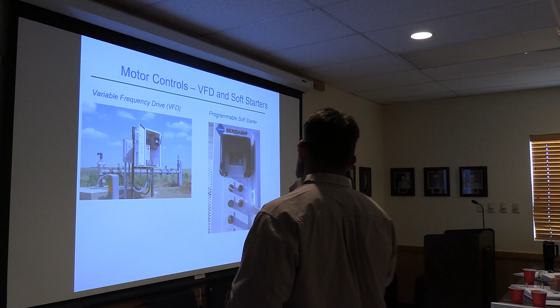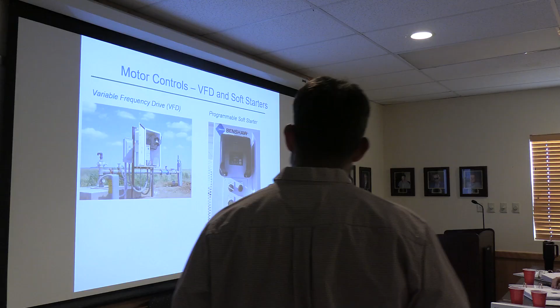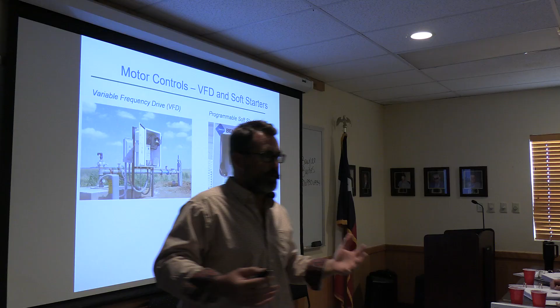So when you put all of, even if it's 15 horses, even if it's 50 horses, you put all of that horsepower online at once, it's going to drag down the motor until it can recover and catch back up with RPM. So you're going to want to use some strategy there to make sure that your start is a ramp, and if you can, that you would slowly ramp into it and avoid that peak, that inrush current. Variable frequency drives are a good tool. You probably are familiar with them now. 10 years ago, it was novel enough that this was a different discussion.